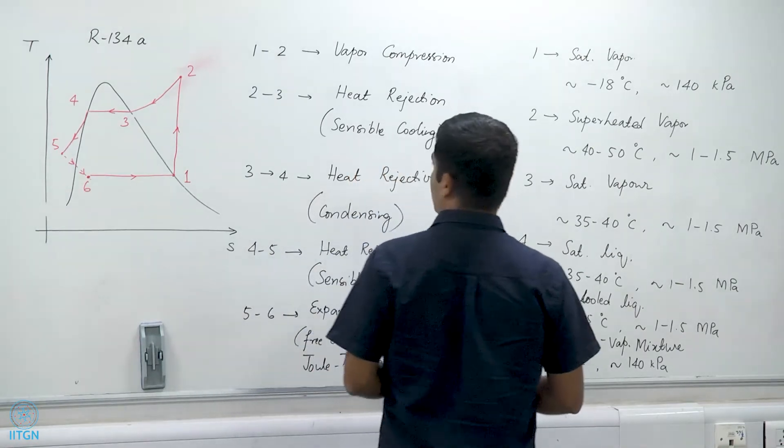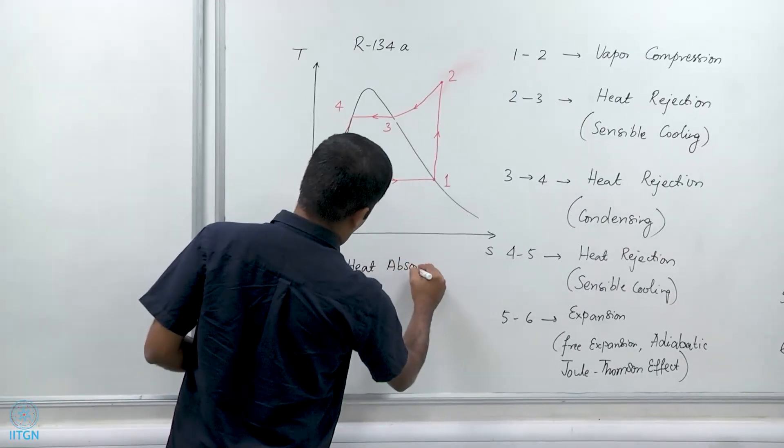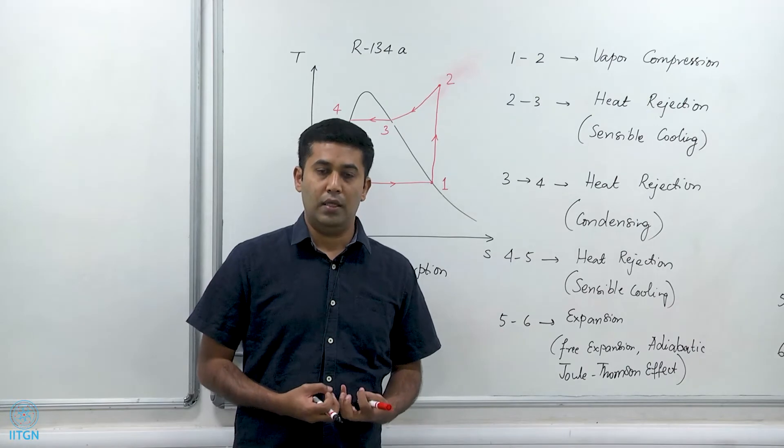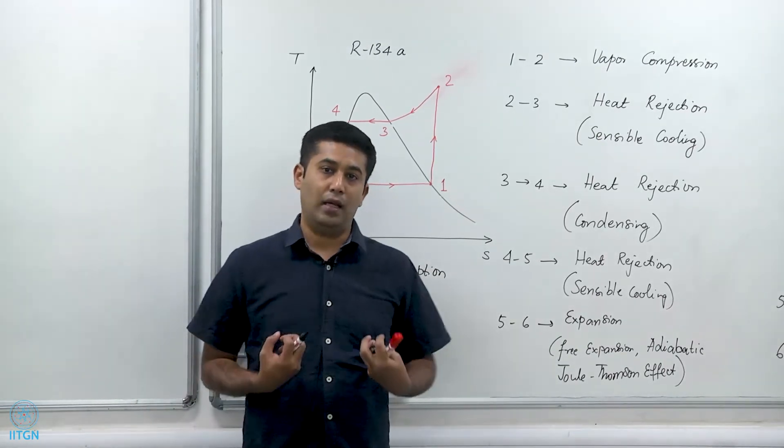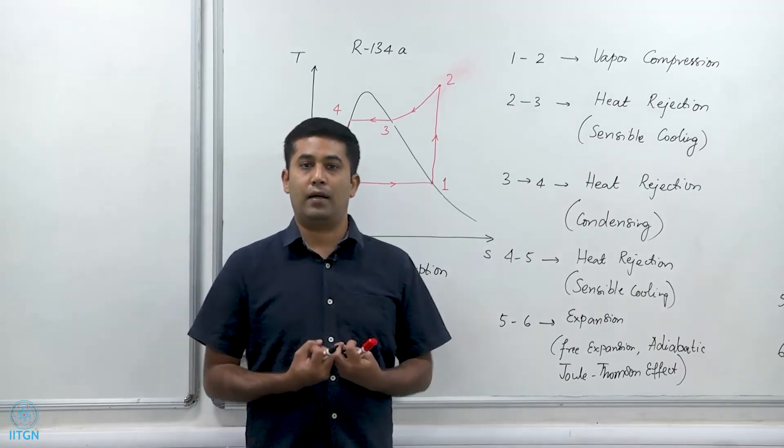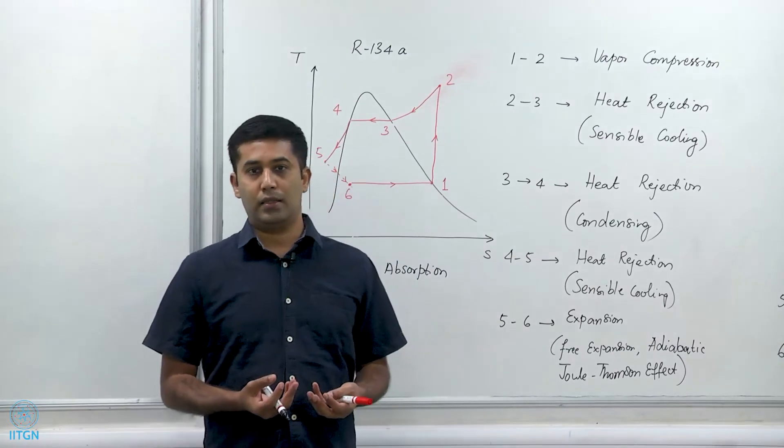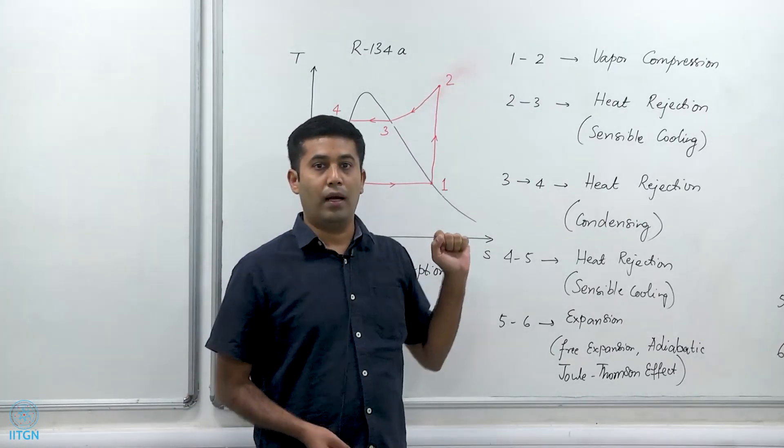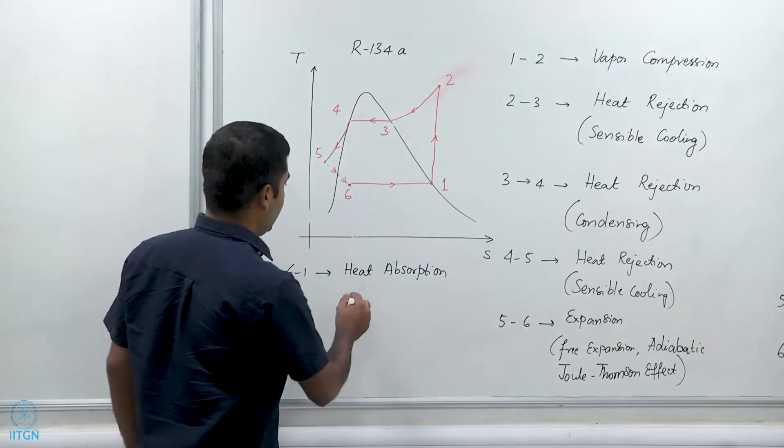Then 6 to 1 is heat absorption. This, in other words, is inside the refrigerator, basically trying to cool down the refrigerator by absorbing heat from the contents of the refrigerator. Or if we are talking about an air conditioner, then this is the unit 6 to 1 that is inside the house, which is called the evaporator. This is where the refrigerant evaporates by absorbing heat from the air inside the room or from the objects inside the fridge and evaporates to become a saturated vapor. The unit that is outside is called a condenser because that is the unit in which the refrigerant condenses from a superheated vapor to a subcooled liquid and in that process rejects heat to the atmosphere or to the room, whichever is the case. So this is the heat absorption step and this is evaporation.